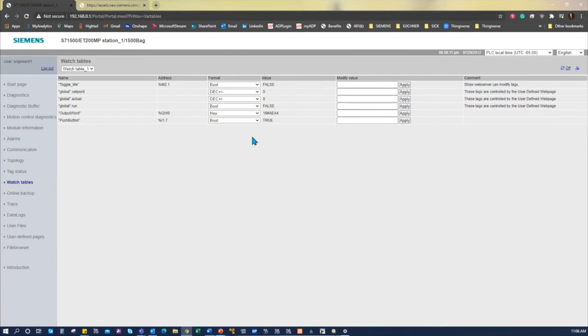And I have full access, so I can modify these values straight from the web server if I wanted to. The watch tables page is often used for diagnostic purposes, and the watch tables are also available directly on the PLC display as well. The tags that you see here have already been configured in the hardware configuration, and depending on whether or not you have access, you can change these tag values right from your web browser.